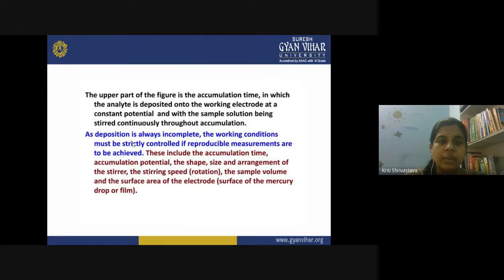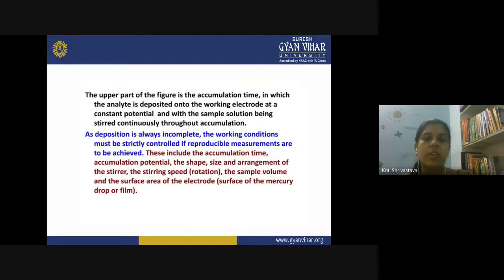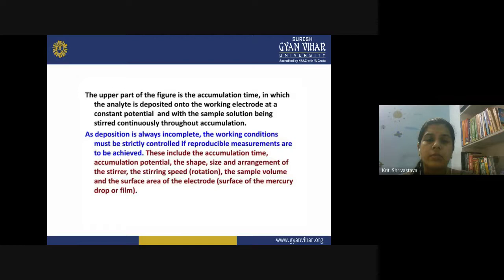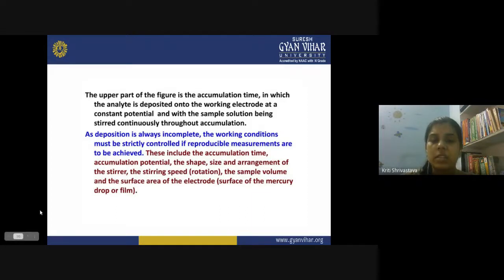The working conditions you need to be careful about include: accumulation time, accumulation potential, the shape, size, and arrangement of the stirrer, stirring speed, sample volume, and surface area of the electrode — whether you are using a mercury drop or film electrode. When you adjust all of them properly, effective accumulation takes place even for trace quantities of the metal ion.